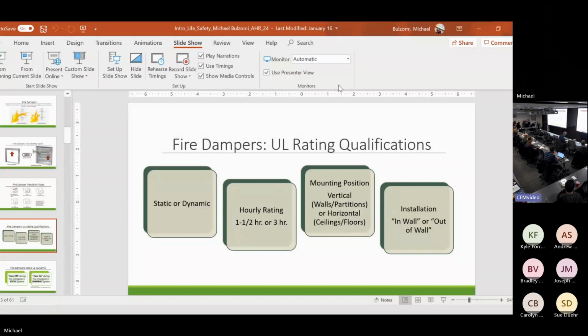So I get a call from a contractor who says, hey, Michael, I need a fire damper. That's the equivalent of me calling my car salesman and saying, hey, Michael, I need a car. He's going to ask me 100 questions. I've narrowed it down to 4. There's 4 major things we need to know to get you in the right area of the damper you need. One, most important, and I'm going to go through each one of these in some slides. The system in which the damper is to be installed, is it considered static or dynamic? That's question number 1. Question number 2, what's the hourly rating requirement of the damper? Hour and a half or 3 hours?